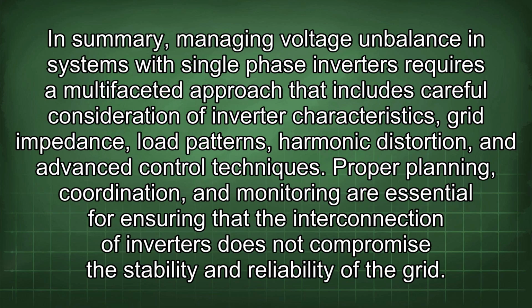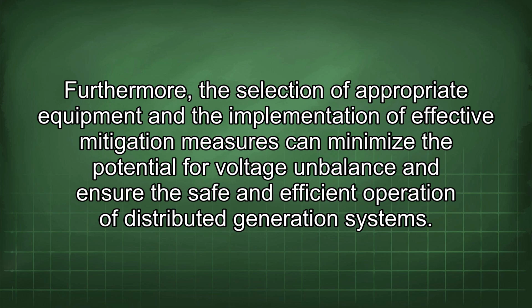In summary, managing voltage imbalance in systems with single-phase inverters requires a multifaceted approach that includes careful consideration of inverter characteristics, grid impedance, load patterns, harmonic distortion, and advanced control techniques. Proper planning, coordination, and monitoring are essential for ensuring that the interconnection of inverters does not compromise the stability and reliability of the grid. Furthermore, the selection of appropriate equipment and the implementation of effective mitigation measures can minimize the potential for voltage imbalance and ensure the safe and efficient operation of distributed generation systems.